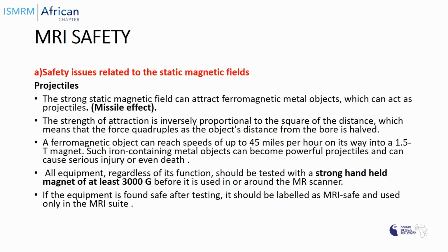Projectiles are one of the safety issues related to static magnetic fields. The strong static magnetic field can attract ferromagnetic metal objects, which can act as projectiles, also called the missile effect. The strength of attraction is inversely proportional to the square of the distance, which means that the force quadruples as the object's distance from the bore is halved. So the closer you are to the bore, the faster this occurs. A ferromagnetic object can reach speeds of up to 45 miles per hour on its way into a 1.5 Tesla magnet.